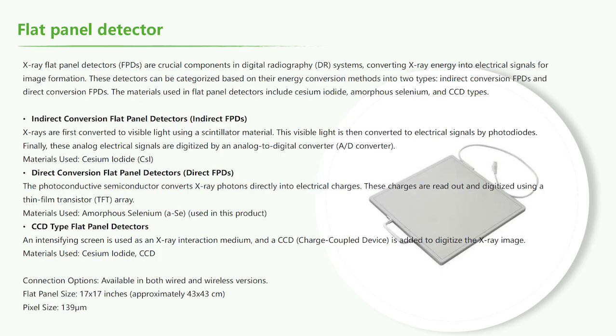In the indirect FPDs, X-rays are first converted to visible light using a scintillator material. This visible light is then converted to electrical signals by photodiodes. Finally, these analog electrical signals are digitalized by an analog to digital converter. The cesium iodide is used in this kind of detector.